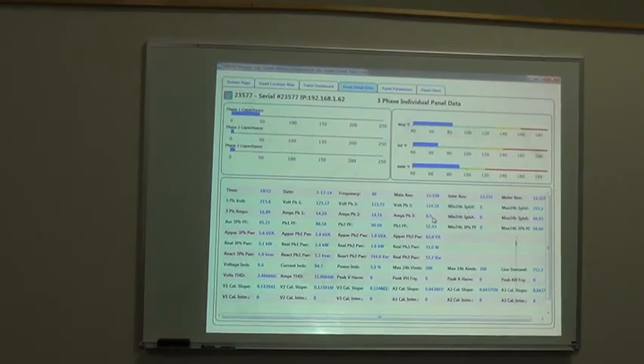So what happens is that when you have too much load on one side, the transformer gets hot, the other side doesn't. Heat in transformers is by far the most important parameter, right? So what happens when one side of it is at 400 degrees, the other side at 100 degrees? Well, you destroy it - not only do you damage it, your efficiency of the transformer goes down drastically.